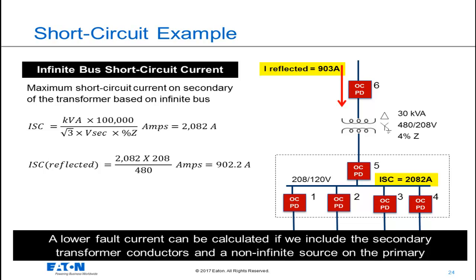Keep in mind that we are omitting some impedance that may change the short-circuit current on the secondary. We're using the worst-case impedance of the transformer. Smaller impedances of the transformer will yield higher secondary short-circuit currents, and larger impedances of the transformer will yield smaller short-circuit currents on the secondary. We're also omitting the secondary conductors that connect the main overcurrent protective device with the transformer.